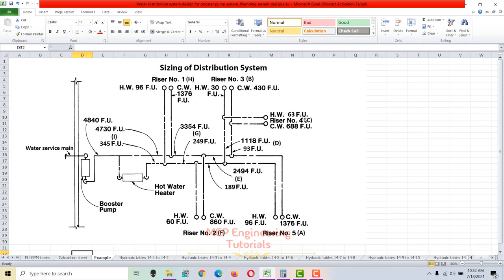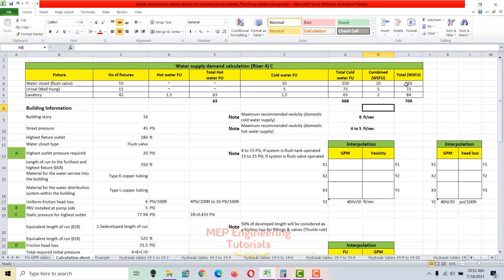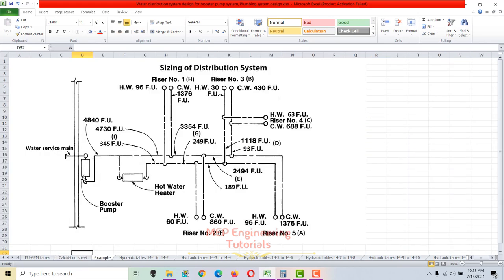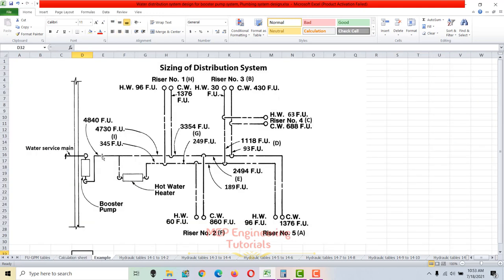At riser 4 (section C), the total hot water fixture units are 63 and the total cold water fixture units are 688. The reason we calculate the total water supply fixture unit (combined) is that the pipe from pump discharge to the hot water heater connection point is sized based on total combined fixture units. For all risers summed, this total is 4840 fixture units.